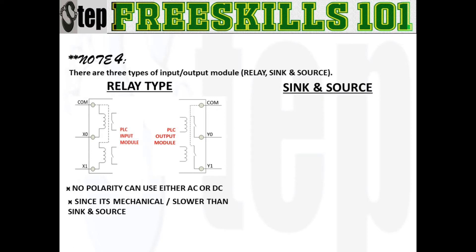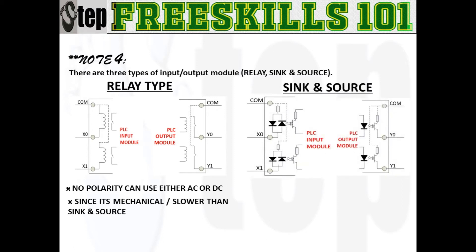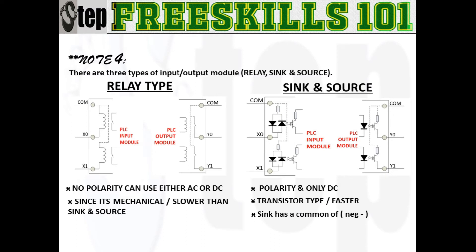Sink and source, or transistor types, are faster but they only cater to DC circuits. Since it's a DC circuit, polarity and wiring is very important and must be given attention. Sink type has a common of negative while the source type has positive. Please take note that 'com' is a short word for common. If your common is positive then your input must be negative, and vice versa. This is considered mostly in DC.